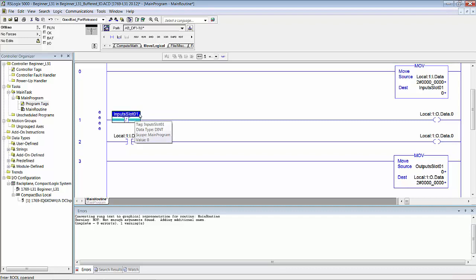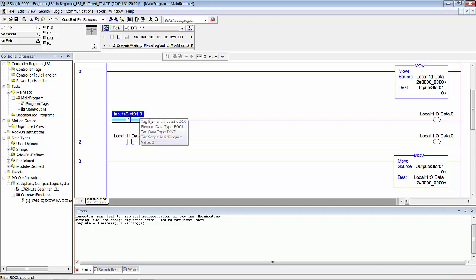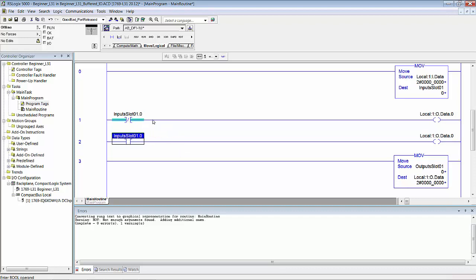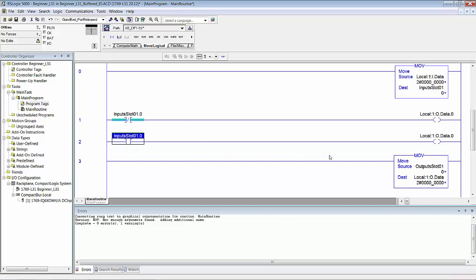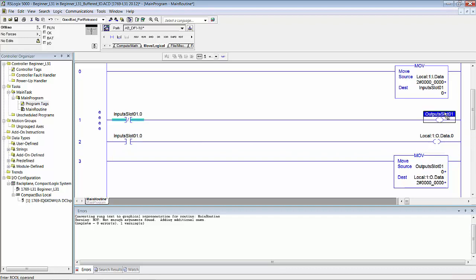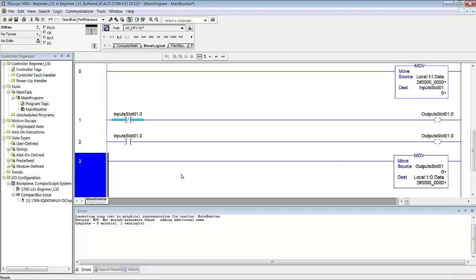We're talking about bit zero. Copy that down here. So now we have InputsSlot01 bit zero, which is the same as Local:1:I.Data dot zero. And then here we want our outputs, and we'll make that. So I think you see what we're doing here. It's really straightforward. Now you have both the inputs and the outputs buffered and isolated from any non-synchronous update of either inputs or outputs.